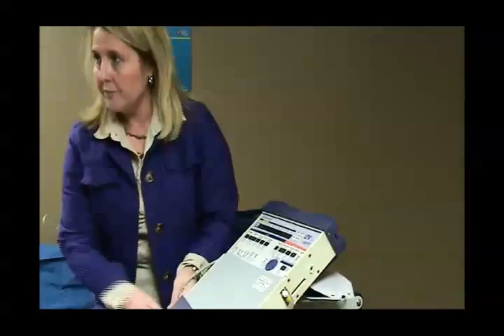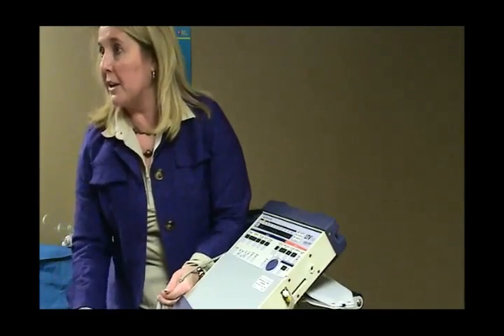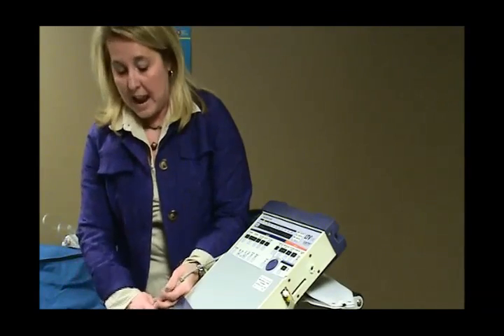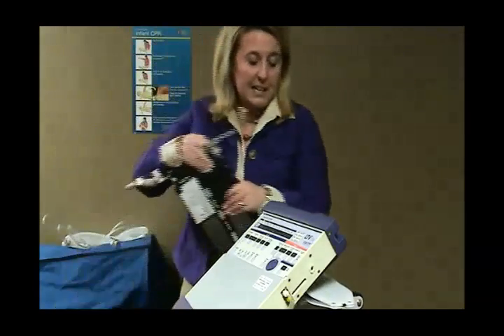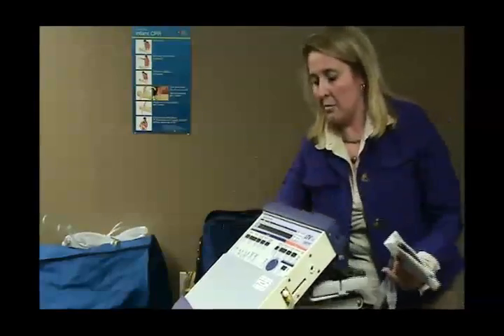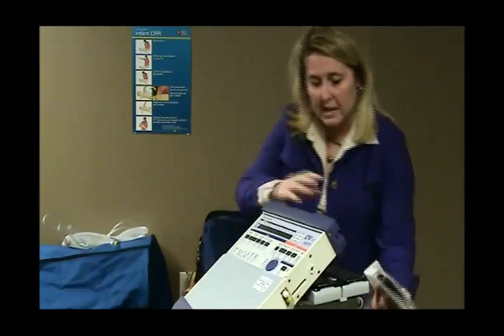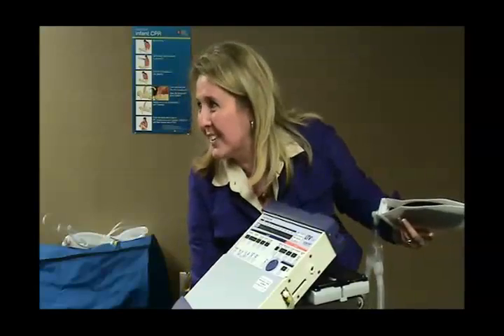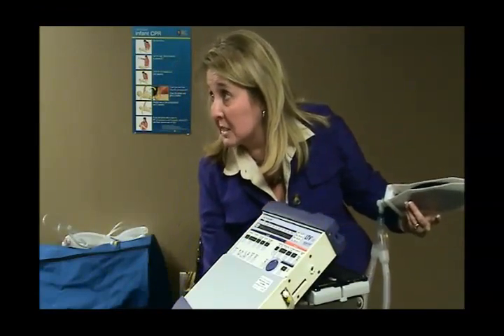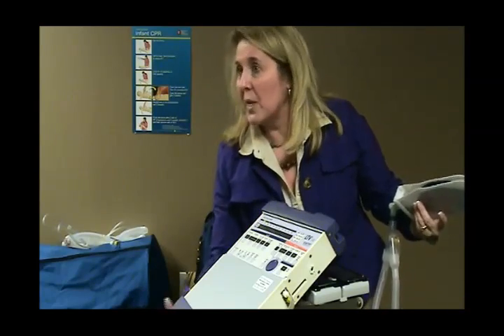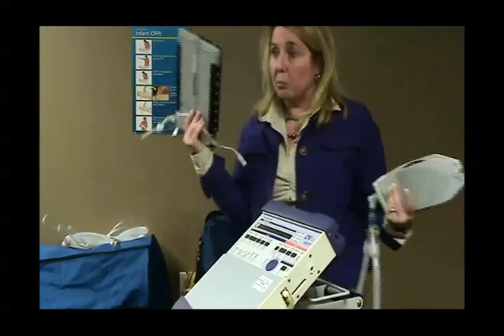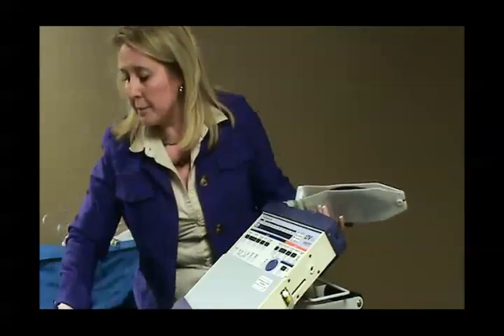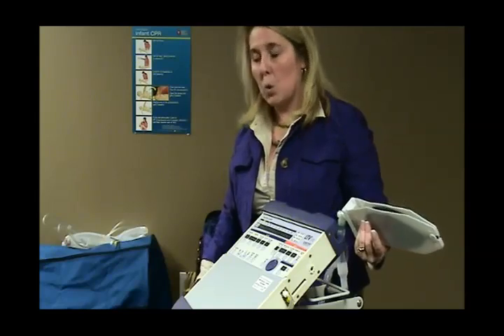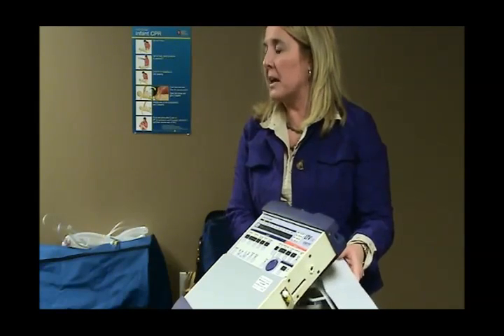Okay? What I don't like to see is this like this. Okay? And then an AC, and this is flinging out here in the wind. Because what's going to happen, that's going to get knocked off, and it's going to snap this. Okay? Or I have seen them where people have tried to do this with it somehow. You know, and then you've got the AC power supply, and you've got this, and there's a bracket that goes on here. So if you're going to use your power supply on your vent with the roll-around stand, you want to have a bracket to slide that into so that it's not just flipping around, because this will inevitably break loose and break the clip or fall off and hit you in the foot, you know. So, bracket. So lithium batteries do not need to be discharged. No. They like to stay charged. That will actually help them last longer.